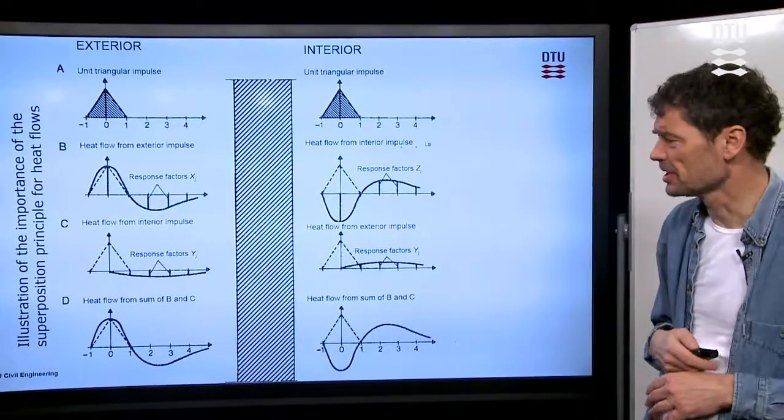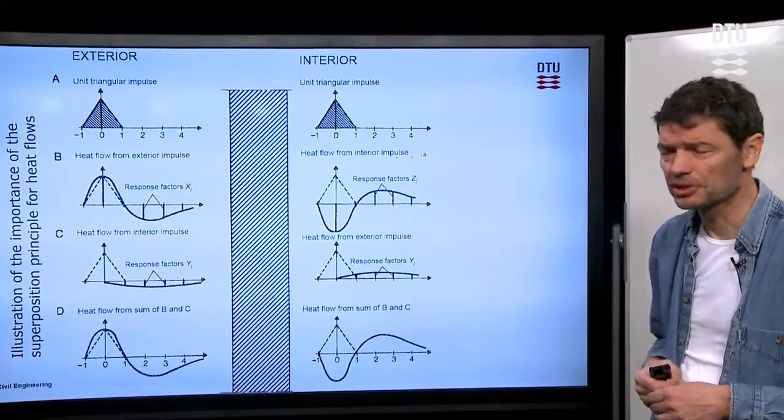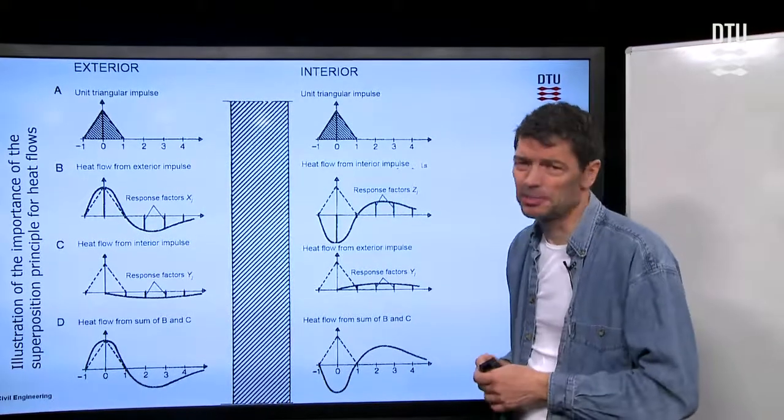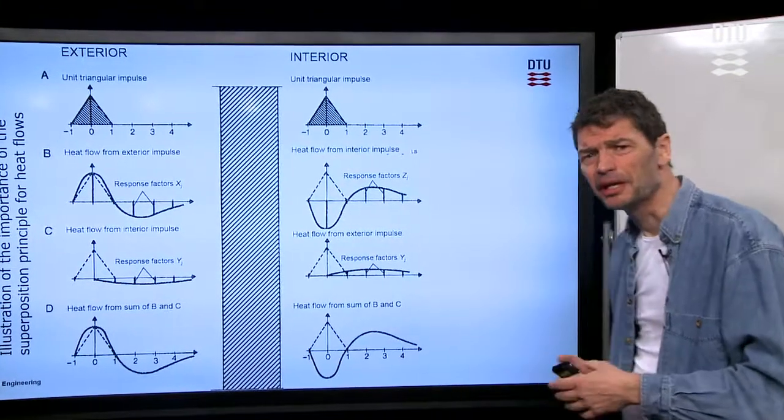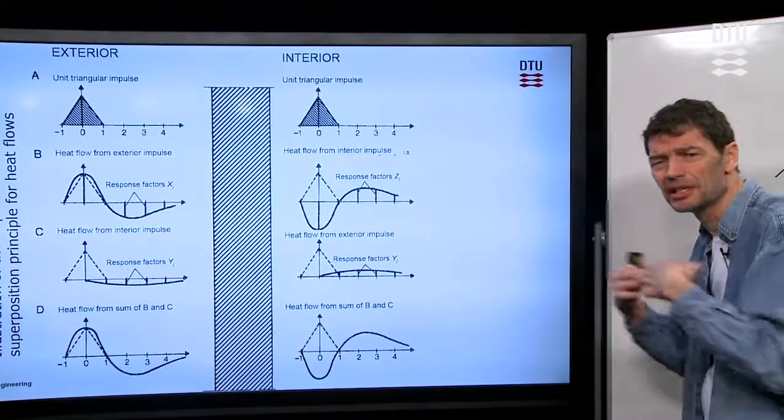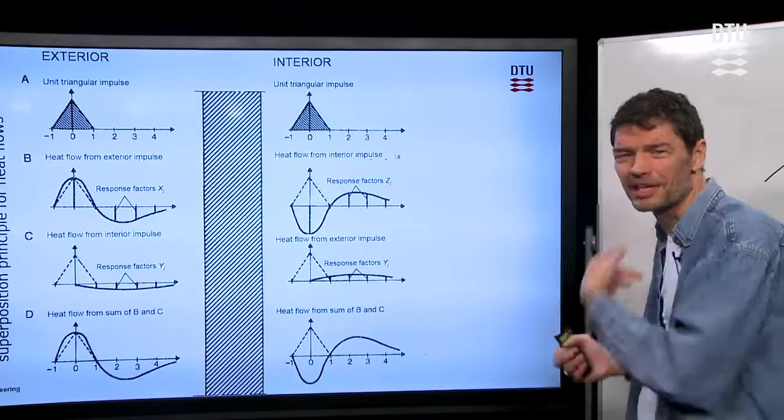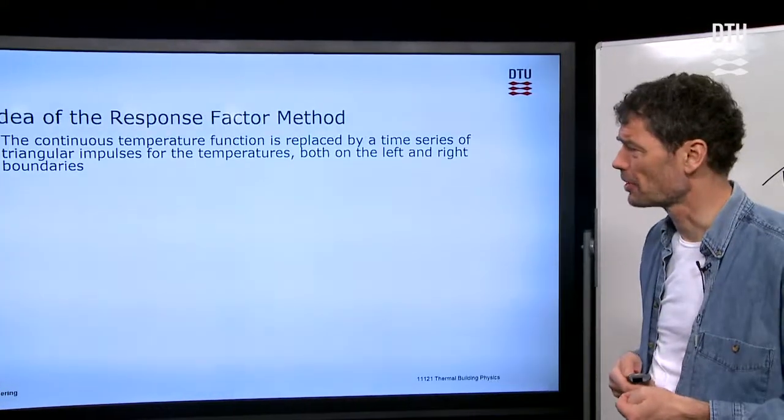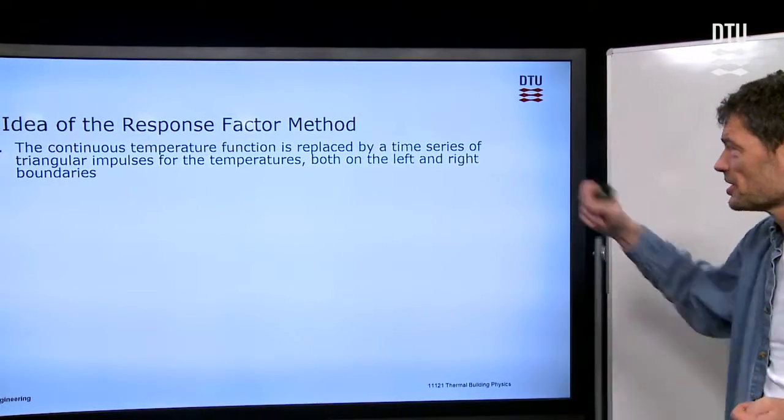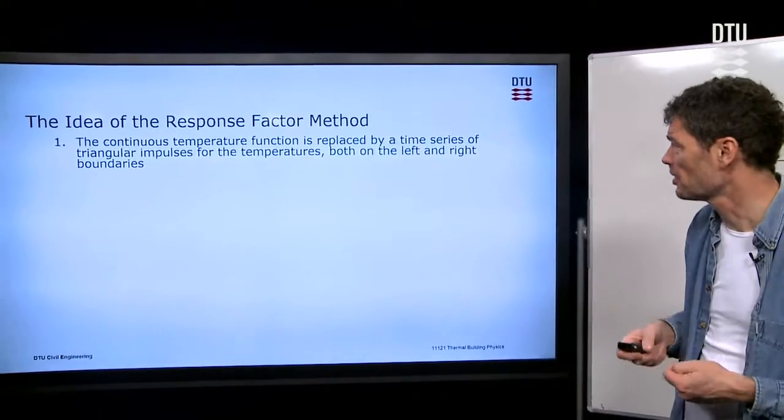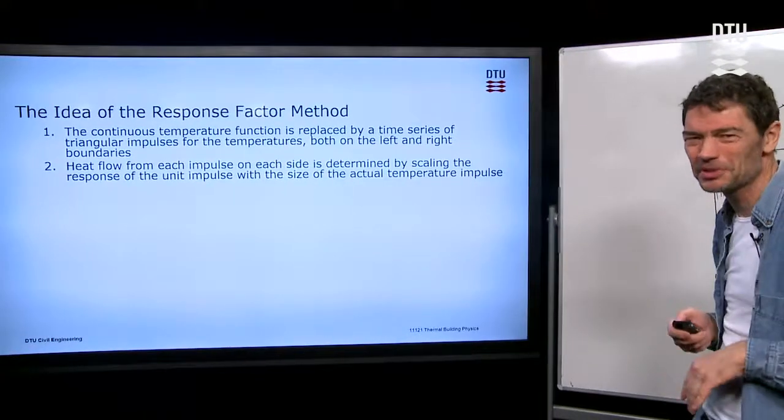Okay. So now we have response factors as time series for the different impulses on the same side and across the wall. And we can add them all up on either of the sides and get some total responses when it's added up. So if we can calculate those response factors as time series, looking to the theory, it's a very efficient way to calculate heat flows in and out of walls when we calculate this in conjunction with the whole building, as I indicated before, and why it's the purpose for what we do.